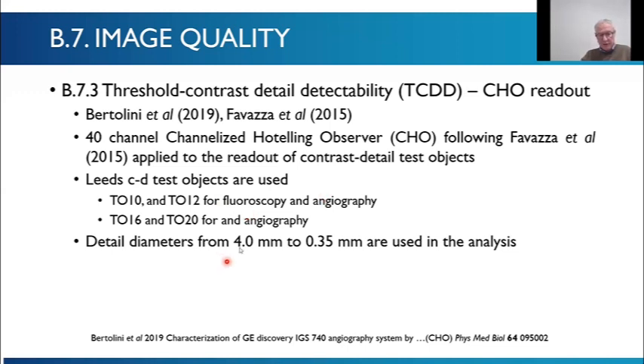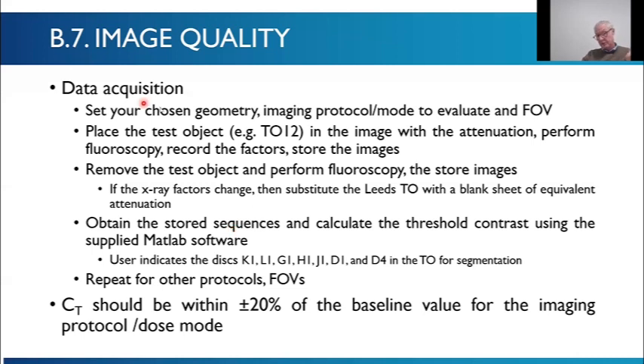This is calculated for detail diameters from 4 down to 0.35 millimeters in the test objects. You can use the TO10 or TO12 for fluoro and angio, or TO16 and TO20 for angiography. Like I said before, you choose your geometry and protocol that you want to evaluate, place the test object on the stack of PMMA, image it, then remove the test object. You may need a blank if your factors are going to change. If your factors do change during fluoro, you would want to put the blank plate in so that you have the same factors with and without the test object.